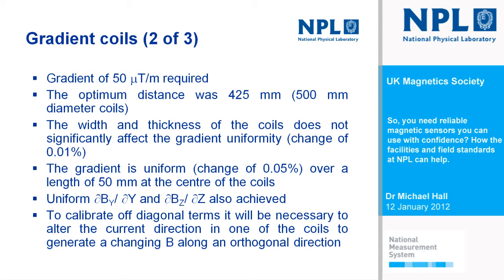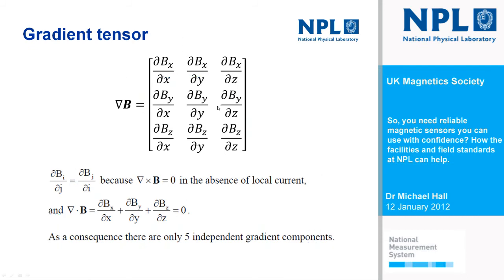But if we go back to that gradient tensor, because we're generating a uniform gradient, by definition these off-diagonal terms are 0. So in order to calibrate these off-diagonal terms, we have to apply a little clever trick. And what we have done is, when operated as a gradient coil, the currents in these 2 windings are in opposite directions. So what we do is to apply the current in these 2 coils in the same direction. So then we go to the world's worst Helmholtz coil system. And in using that approach, we can generate off-diagonal terms. And I'll show you some profiles that we get, and it gives us a means of being able to calibrate off-diagonal terms for the gradiometer being calibrated. And that's summarised there in that last point.